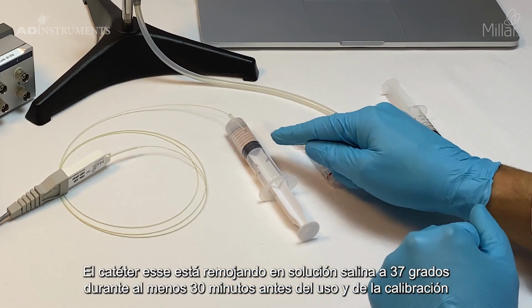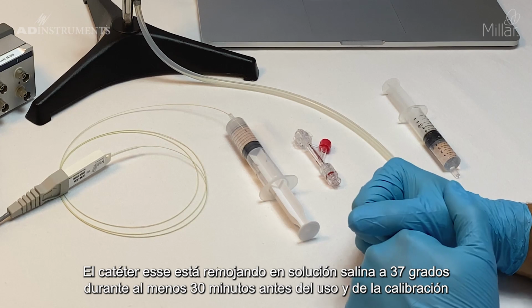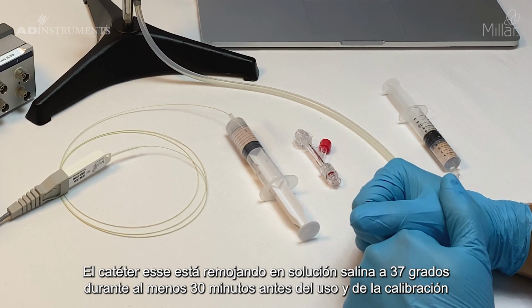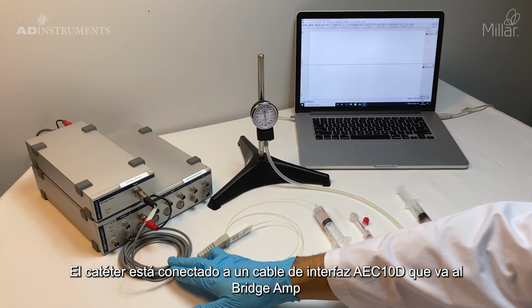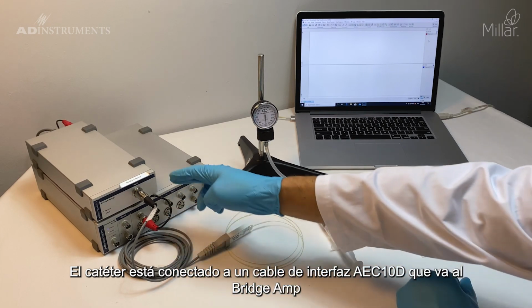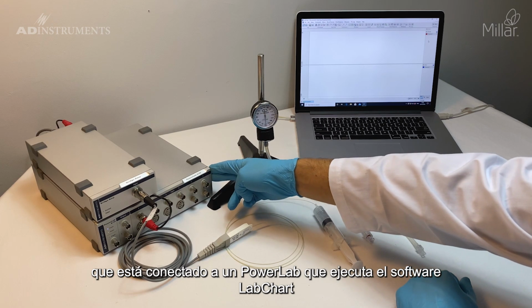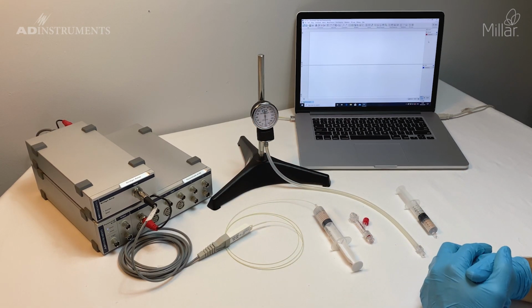The catheter is soaking in 37 degrees saline for at least 30 minutes before use and before calibration. The catheter is connected to an AEC 10D interface cable, to a bridge amp which is connected to a PowerLab which is running LabChart software.